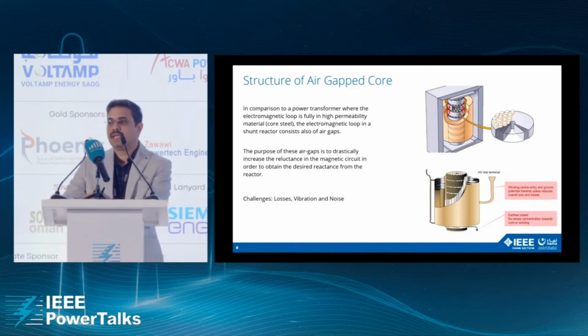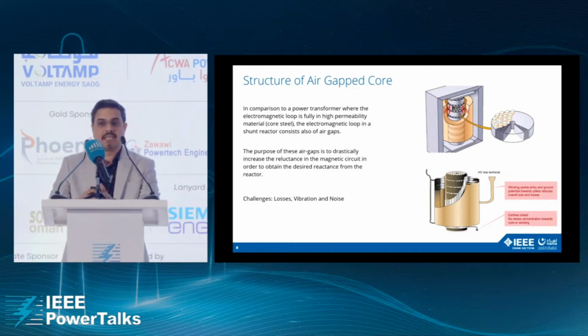Of course, when you are building a core with very high reluctance, there are some challenges: the no-load losses are higher, and there are a lot of vibration and noise challenges. So this is something that has to be taken care of while manufacturing a reactor. The transformer is relatively simple in construction compared to a reactor, because it doesn't face so many of these vibration and noise challenges.